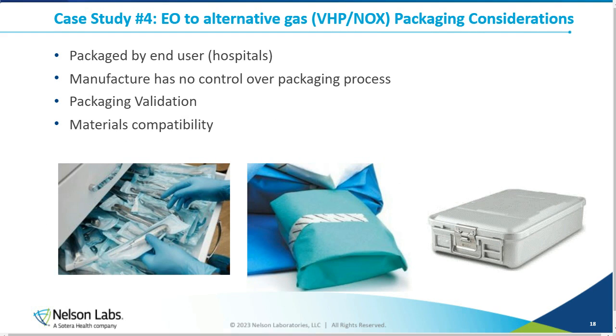That's an interesting thought with these alternative methods of sterilization, is that you just don't have the volume capacity that you would with EO or with radiation. And so that puts you in a bit of a quandary. If you're doing low batch manufacturing, it would be possible for you to sterilize these one box at a time, essentially. There's a bit more materials compatibility to look at. Some of these alternate gases are not as compatible as EO with certain material types, so you may be using different types of packaging. Another option would be to sell your product non-sterile with the expectation that it will be sterilized in the hospital setting.